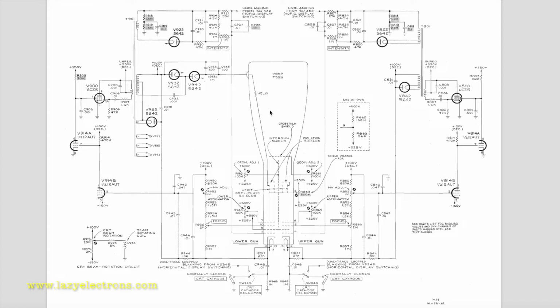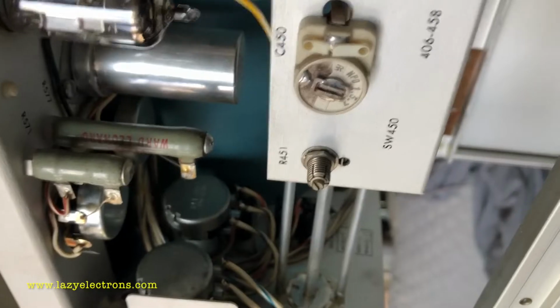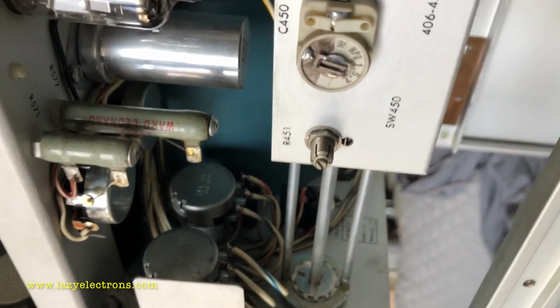So that is again used to achieve some very specific CRT qualities, and beam qualities rather, and keep the high voltages at a controlled limit. Again, the discussion of that is beyond the scope of this video, but there is information available on TekWiki in case you're interested. One more word of caution in case you're working on it.